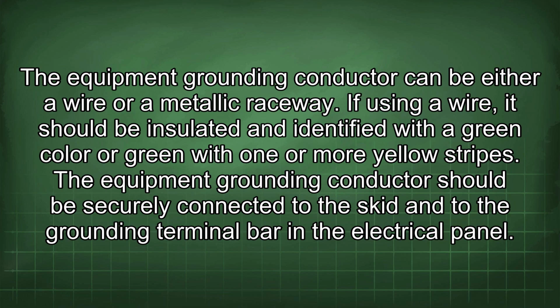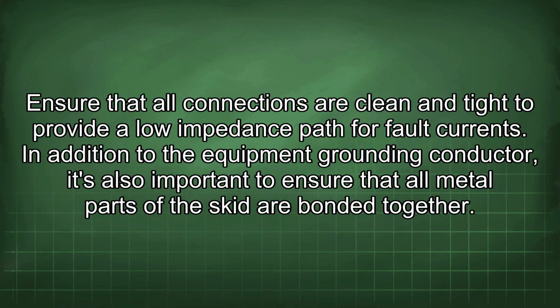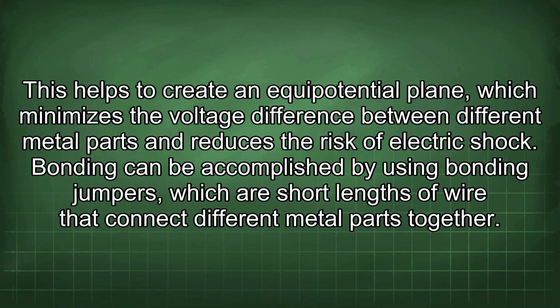If using a wire, it should be insulated and identified with a green color or green with one or more yellow stripes. The equipment grounding conductor should be securely connected to the skid and to the grounding terminal bar in the electrical panel. Ensure that all connections are clean and tight to provide a low impedance path for fault currents. In addition to the equipment grounding conductor, it's also important to ensure that all metal parts of the skid are bonded together. This helps to create an equipotential plane, which minimizes the voltage difference between different metal parts and reduces the risk of electric shock.